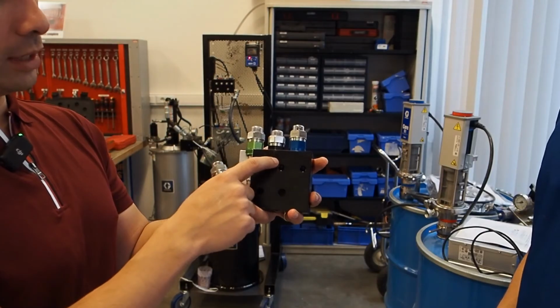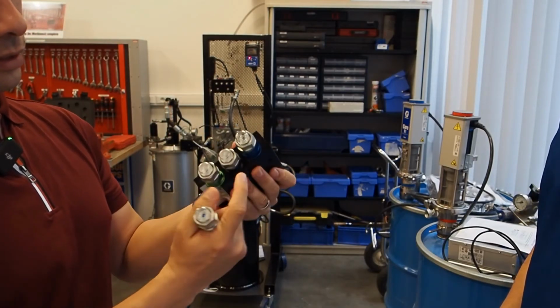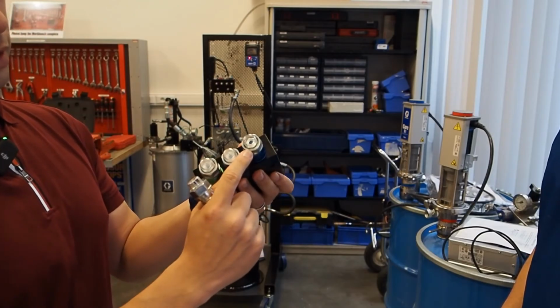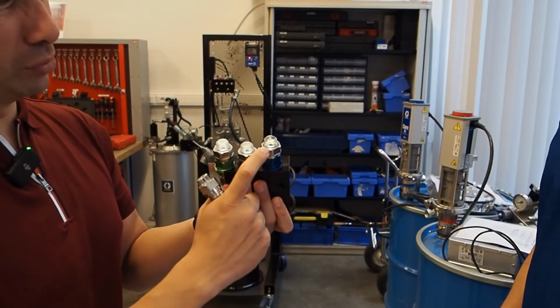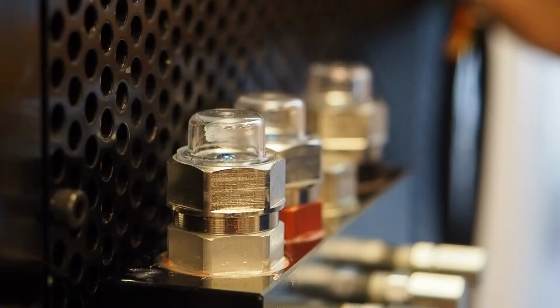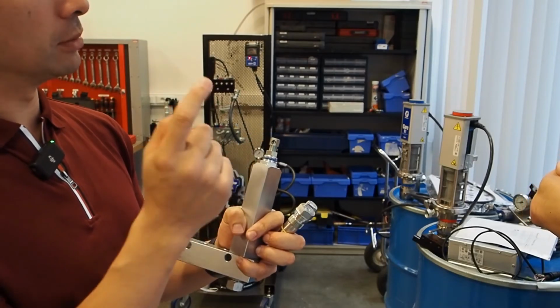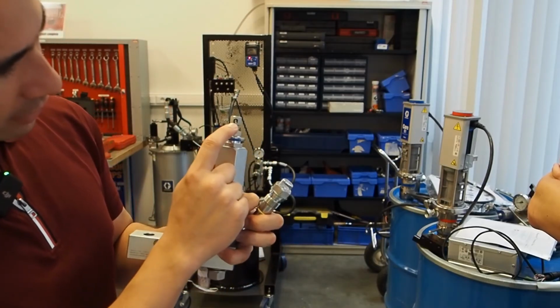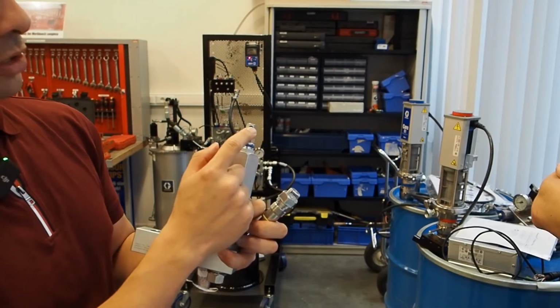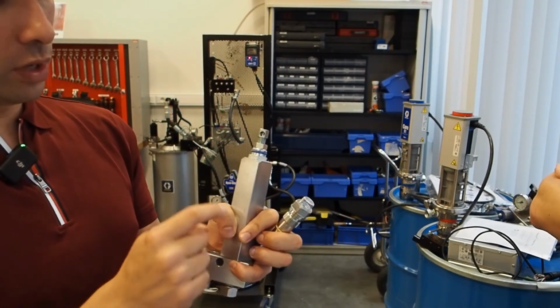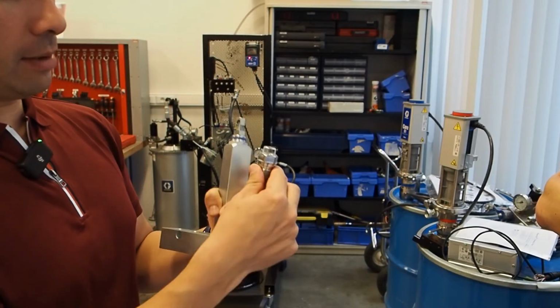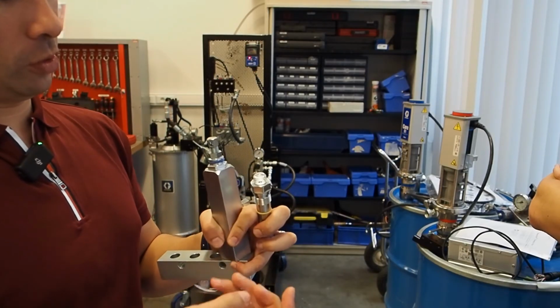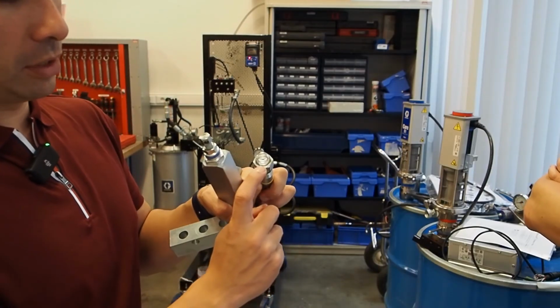The other interesting feature on these is the firing pin. For starters, it's handy that it's colored blue, because often these things are not colored, and it's a little bit difficult to see when they actually fire. But you can see up here, these ones will poke up when the grease is fired. Now, on the legacy systems, which is not just the Graco systems but others as well, generally what you'll see is that the pin will move. In the case of the Graco system, it'll move down. So that's how you can tell where the grease is actually being injected by one of these. So it's a similar concept, which is in some senses good because everyone is used to it, but in this case, the pin is going to go up.